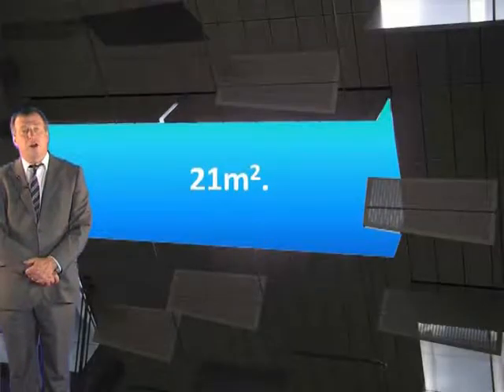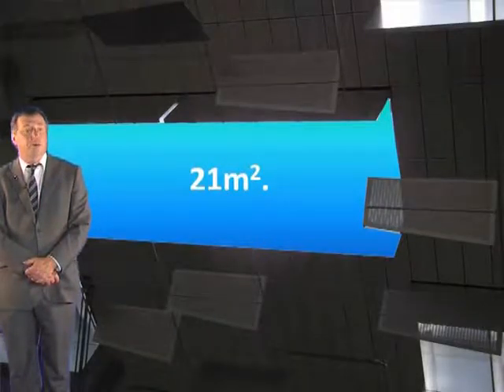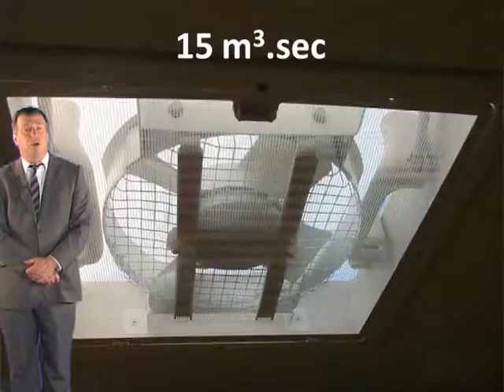If the installed capacity is greater than the required capacity, then the base of the smoke layer will simply remain a little higher in the reservoir. For natural ventilation, the required exhaust capacity will be a specified area of ventilation, and for mechanical, it will be a volumetric flow rate.